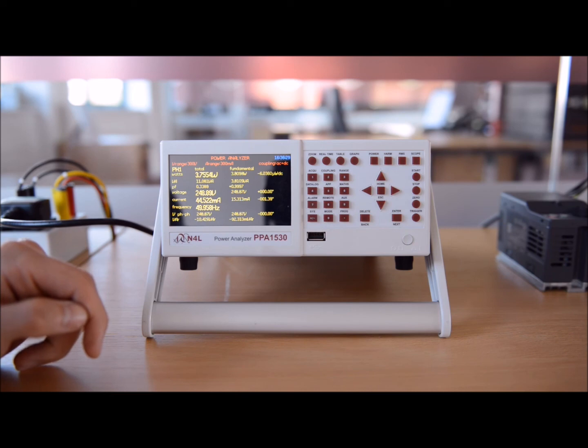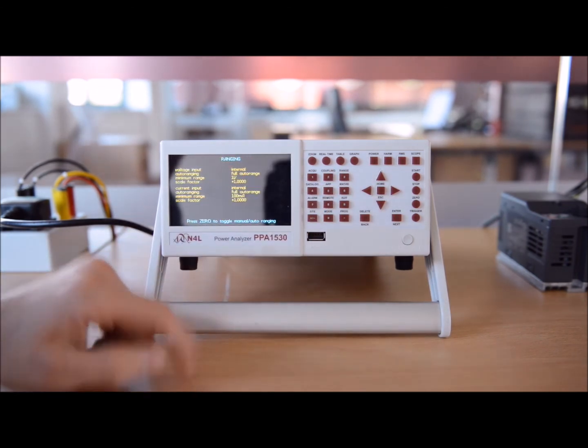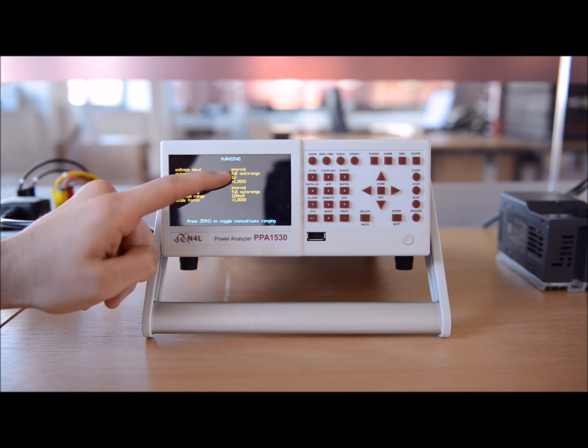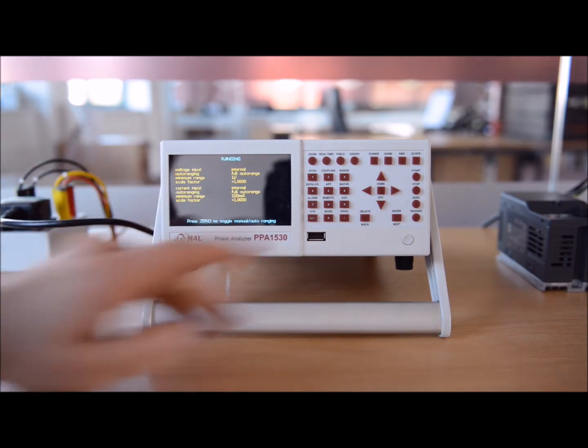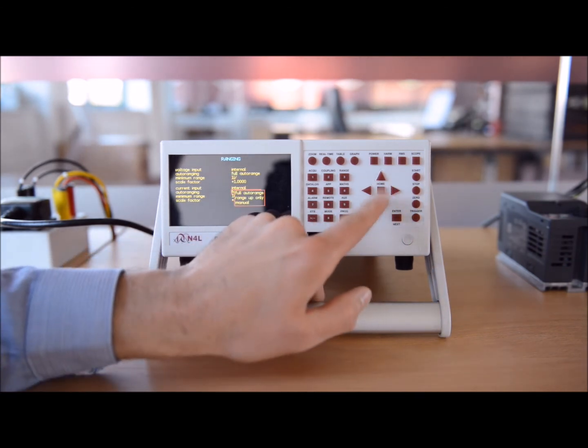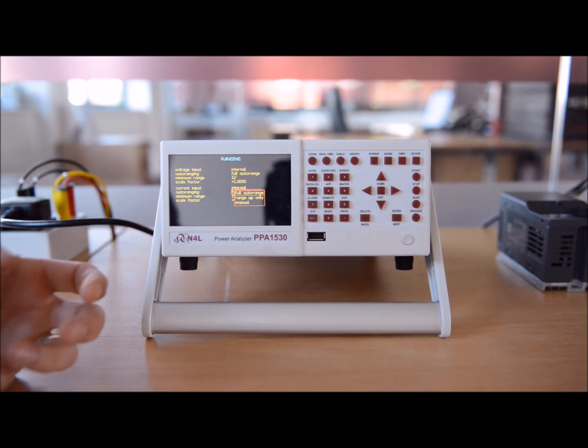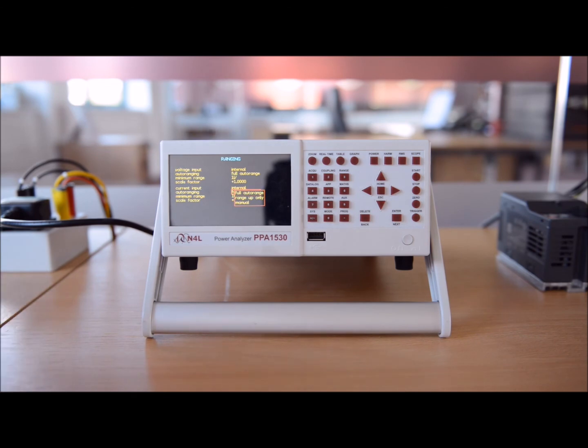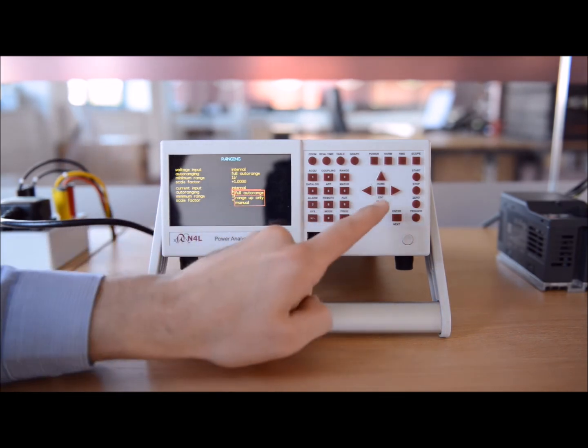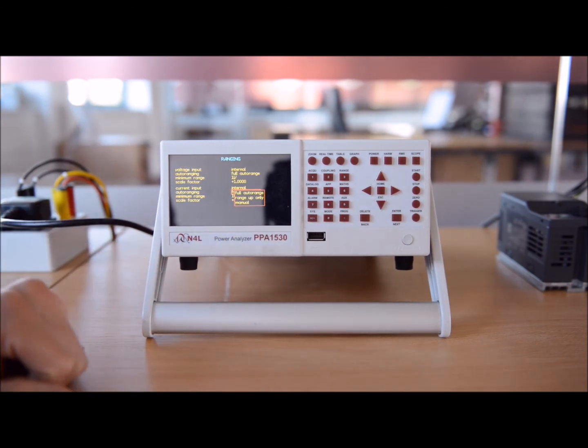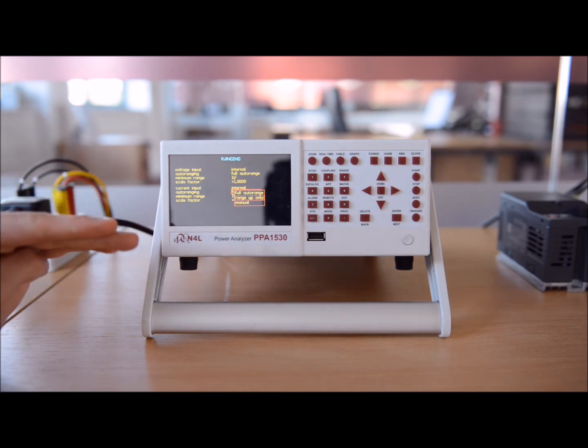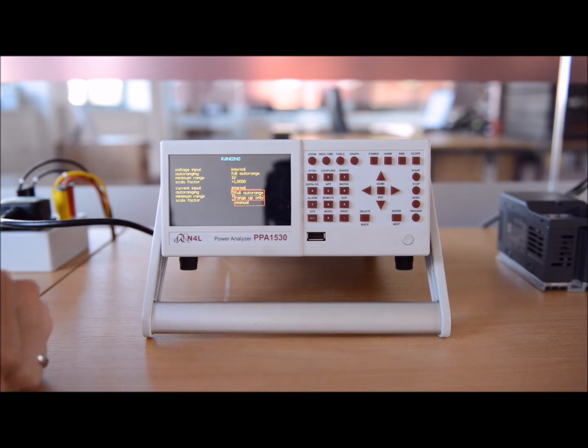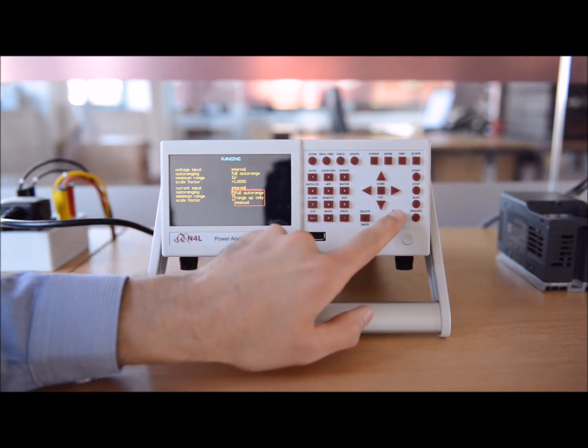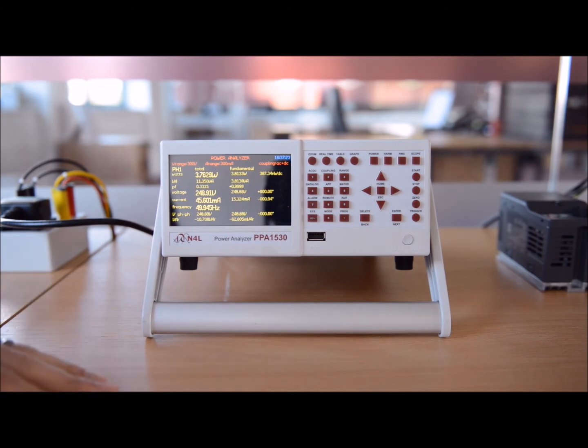Now on the voltage and current side here, we're using the internal voltage attenuator and the internal current shunt. Now if we look in the range menu, you can see I'm using internal, and I'm going to allow the power analyzer to range up and down as it wishes. Now if you were doing an inrush measurement, for example, and you wanted to measure how much inrush current there is to the device when we either first plug it in or when we turn the output on, then we'd look at the range up only and run the test a couple of times in order to range up to the top range, and then we leave it on the top range so that we're not ranging during an inrush test. What I'll do is in a later video take you through how to measure inrush current with a power analyzer. But for today we want a steady state efficiency measurement, so let's leave it like that.